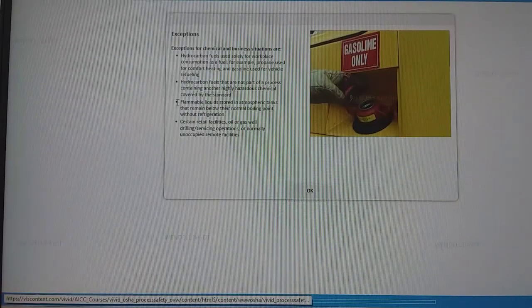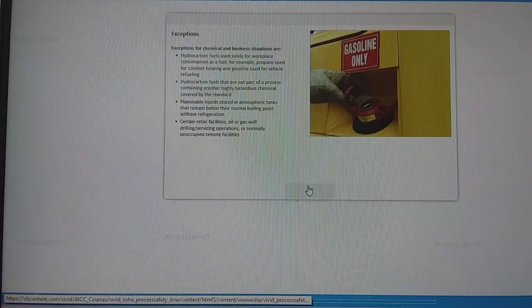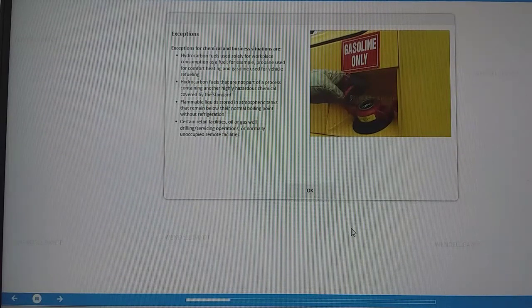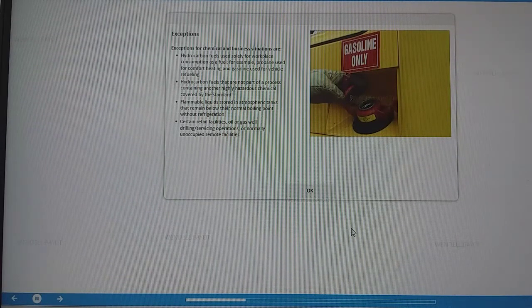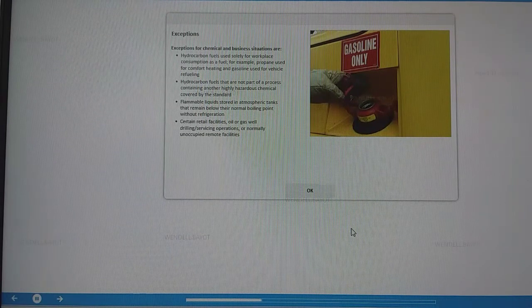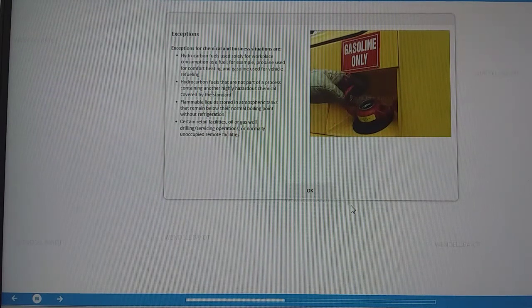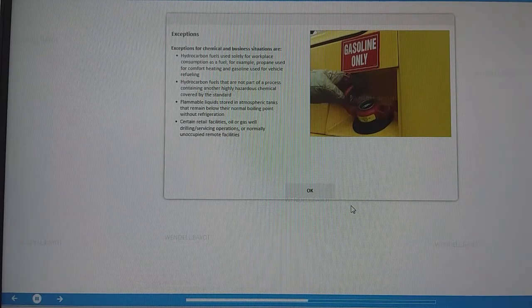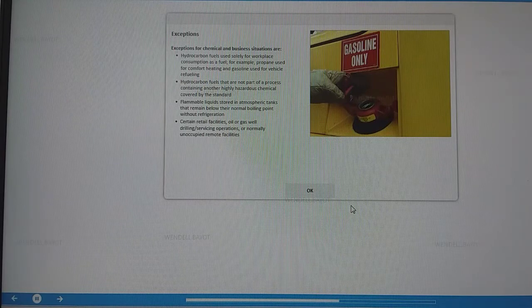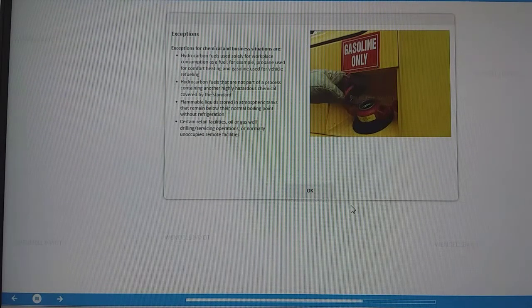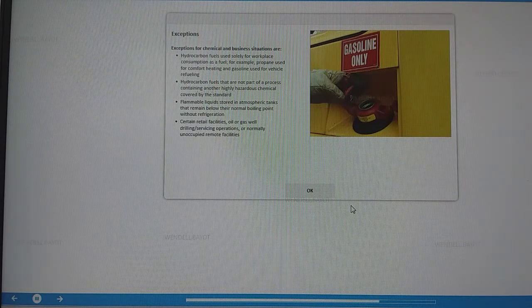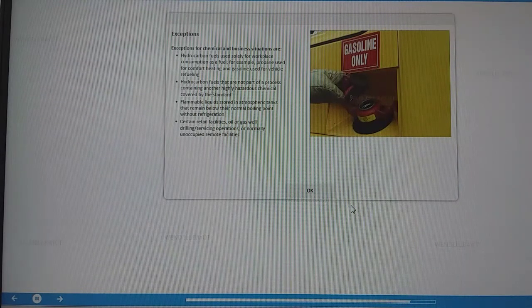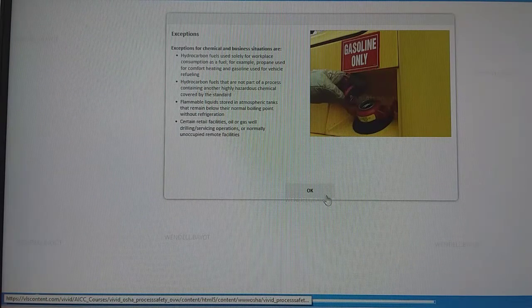Exceptions include hydrocarbon fuels used solely for workplace consumption as fuel, such as propane used for comfort heating and gasoline used for vehicle refueling. Also, hydrocarbon fuels that are not part of a process containing another highly hazardous chemical covered by the standard, flammable liquid stored in atmospheric tanks that remain below their normal boiling point without refrigeration, certain retail facilities, oil or gas well drilling or servicing operations, or normally unoccupied remote facilities.